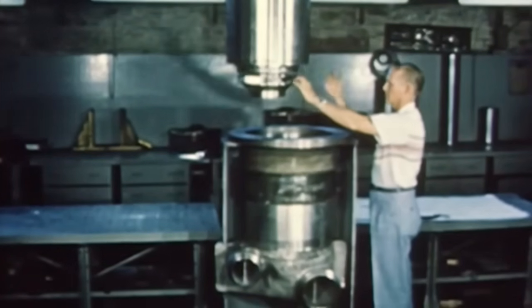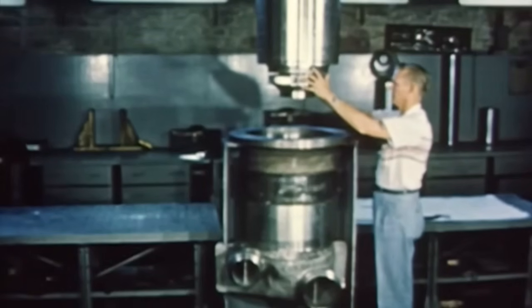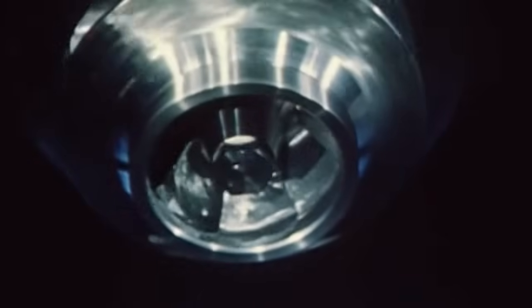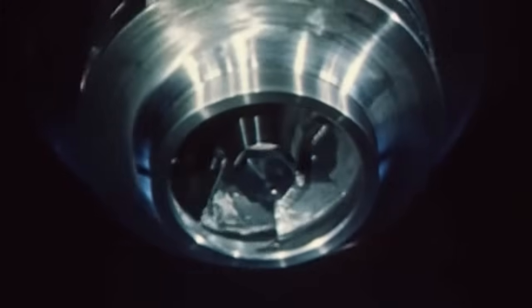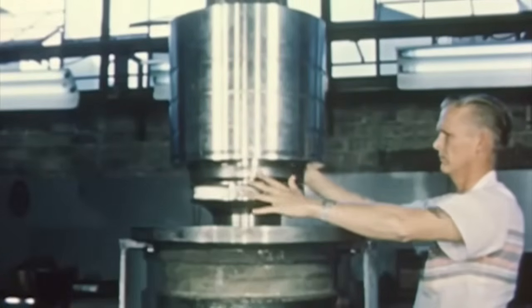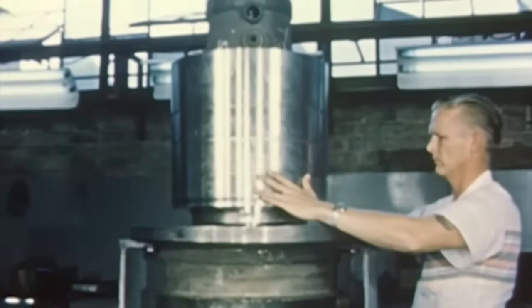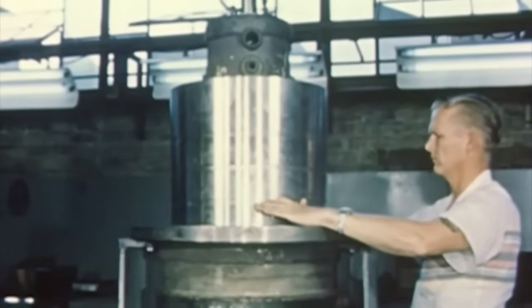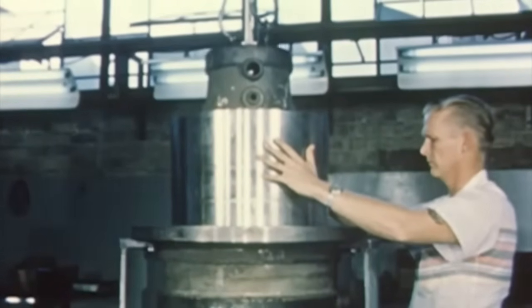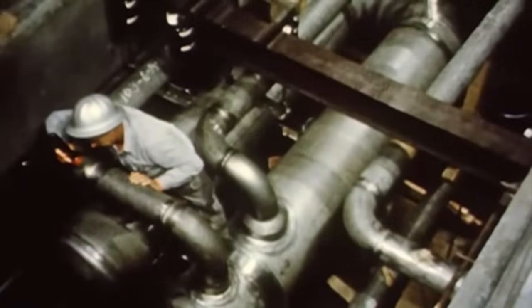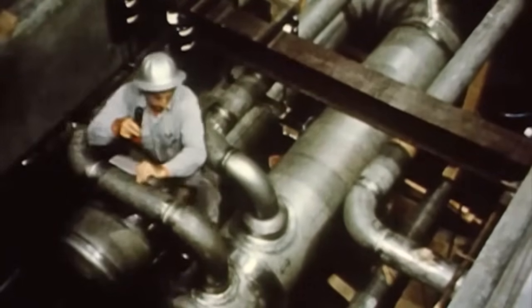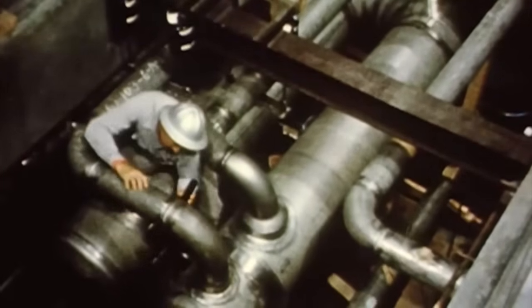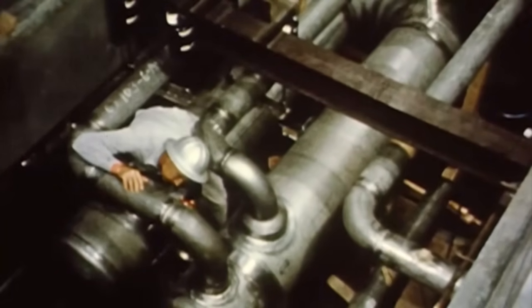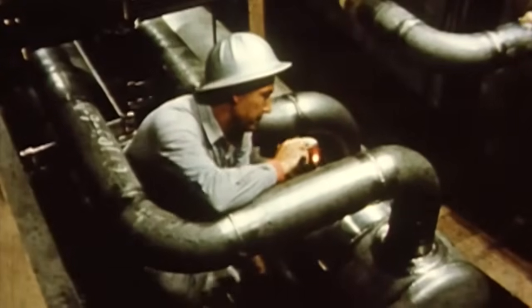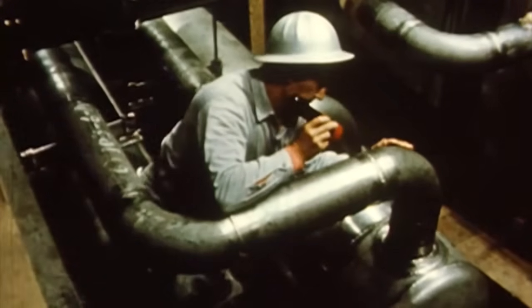The sodium pumps are modified hot oil pumps designed for high temperature service in oil refineries. The principal modifications consist of vertical mounting and the addition of frozen sodium seals at the shaft and at the case. This pump will deliver 1,285 gallons a minute against a 130-foot sodium head. The intermediate heat exchangers employ a shell and tube counterflow arrangement designed in a U shape. This configuration conserves space and minimizes thermal stresses.